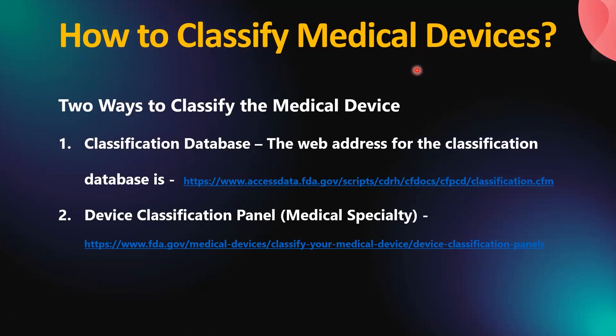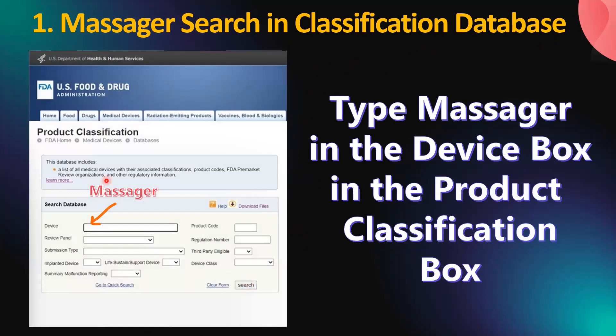Besides classification based on risks, there is also a need for product classification of your medical device. There are two ways to classify medical devices: one is through the product classification database, with the web address available in the comments section; and the second is through the device panel based on medical specialty, with the web address also in the comments section. We would like to share with you a demo of both these searches.